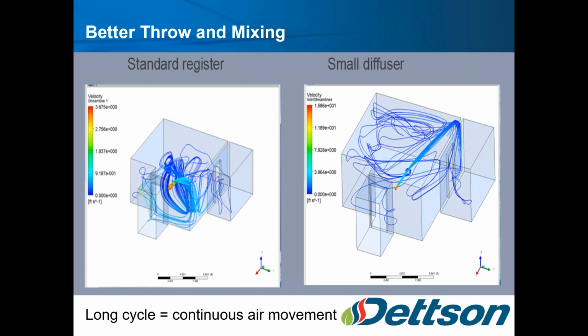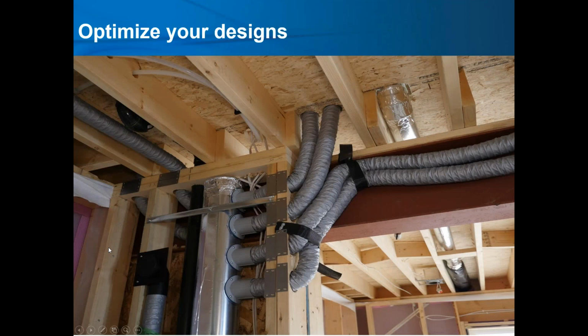It uses the ceiling as a main plenum, and with that 9 feet of throw paired with equipment that's running at low CFM over longer periods of time, you can see on the left the 3 feet of throw from a traditional system, and on the right 9 feet of throw with the low to medium velocity system. So much better mix and much better conditioning for rooms, and this is hugely important especially where we've had the problem children in the industry, right? The bonus rooms above the garage, stack effect for townhouses. So really addressing those issues and solving a lot of the problems that we were traditionally seeing.